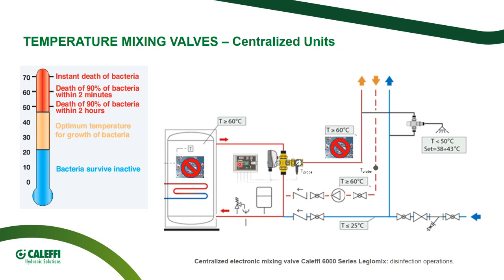The digital regulator of the valve or the BMS system will be programmed for it, and they will state whether the thermal disinfection will be correctly achieved or not. In case of hot water flushing of the recirculation system, the user, of course, has to be aware of it, but in any case, if you remember, we put a further thermostatic mixing valve to protect the final user. So even in case of thermal recirculation, thermal disinfection, my users will be safe anyhow.